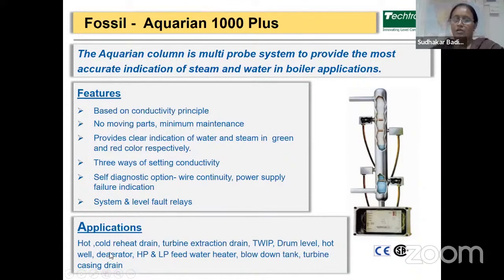The applications are hot and cold reheat drain, turbine extraction drain, TWIP, drum level, hot well, deaerator, HP and LP water heaters, blowdown tanks, and turbine casing drain. So in the picture you can see, this is a column with four probes and the controller along with it. And on the controller, you will get the indication of water and steam.